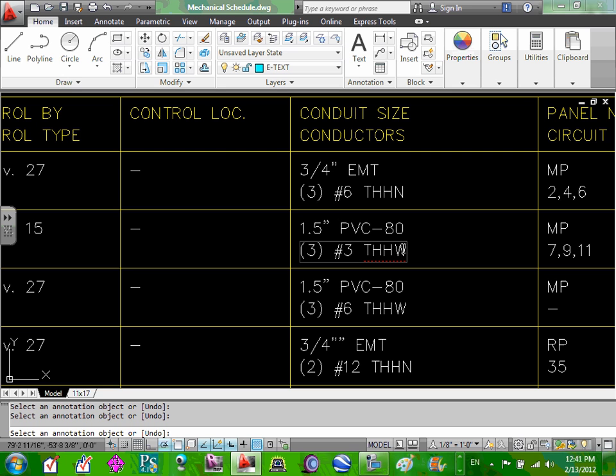I bet you went from a 60-degree column. If it's mechanical equipment like this, guys, even if the amp is lower than 100, 99.9% the lugs are rated for 75. I'm telling you, you go to 75. If it's mechanical equipment like these 3-phase. Any question about that? So I went to 75-degree and sized it.